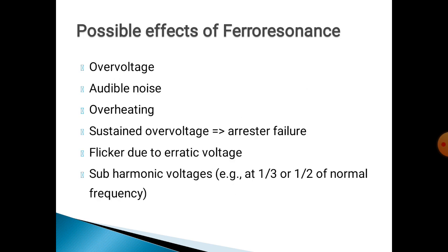And the next important topic is possible effects of ferroresonance. First is overvoltage, audible noise, overheating, sustained overvoltage, failure of lightning arresters, flickers due to the erratic voltage, and the final one is subharmonic voltages, for example at 1/3 or 1/2 of normal frequency range.